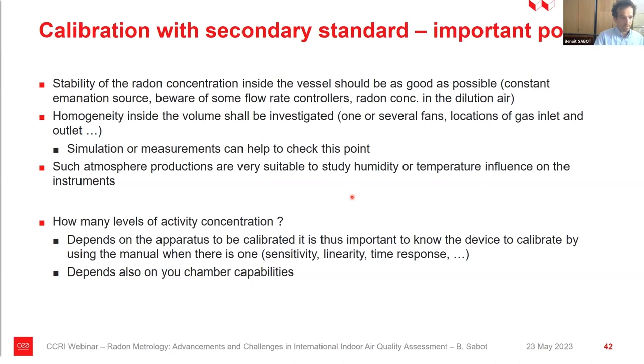Of course, it always depends on the chamber capabilities. I know that some colleagues from other national labs like ENEA and PTB made a huge chamber where they can place a lot of detectors and make other kinds of studies. But of course, when you have a huge chamber, then you have other challenges to produce the atmosphere, and especially a homogeneous atmosphere that is stable with time.